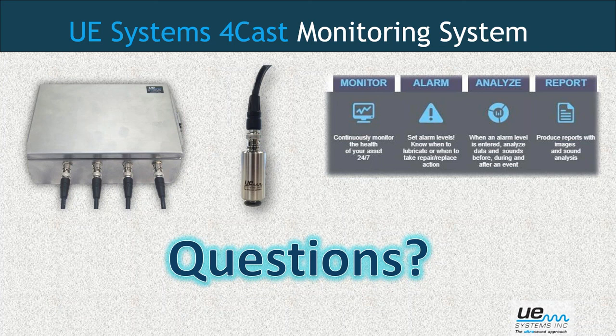As far as wireless, we can take a wireless router out of the 4Cast box and put a wireless router on the computer, so you can send the data and sound files via Wi-Fi. But the sensor itself has to be wired - it needs power, getting it from the box. We've got people using them on robots, on cranes - it's easy to mount them, you just have to watch your cable lengths. In some cases people are using the sensor with just an 8-inch or 12-inch cable, putting the box and sensors right on the moving asset. So that's an option as well.